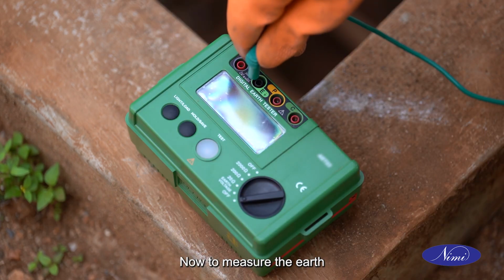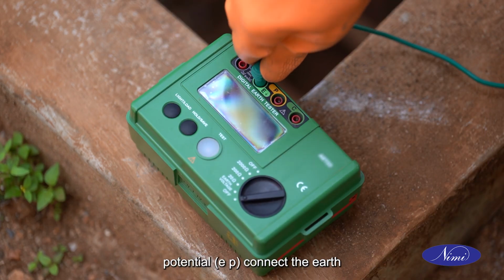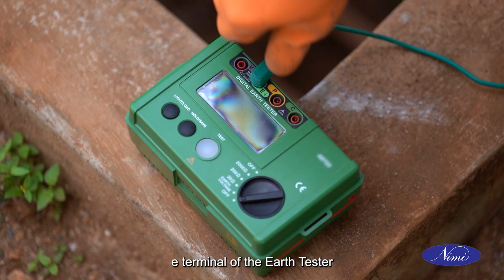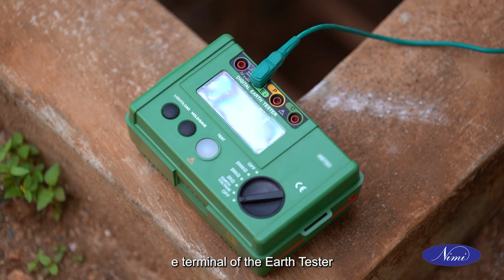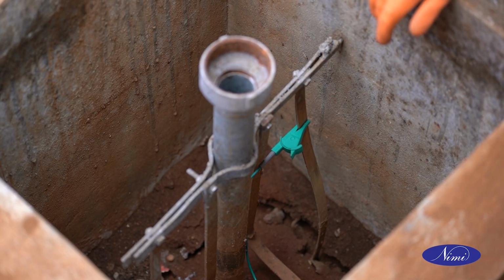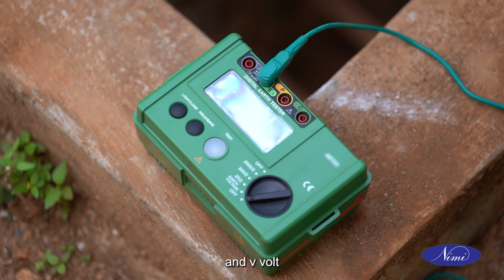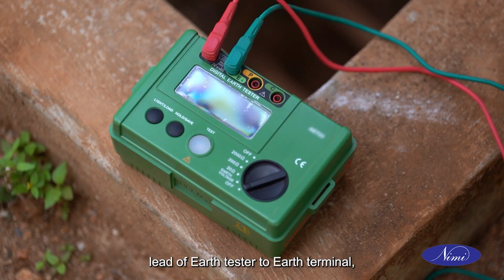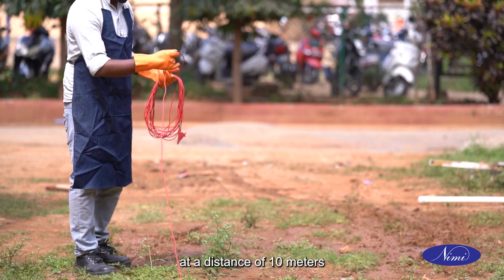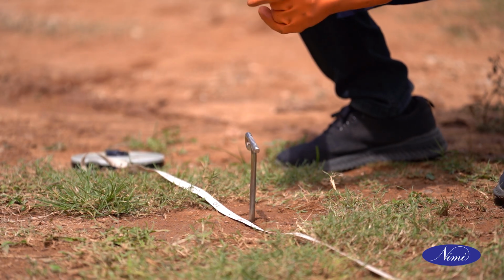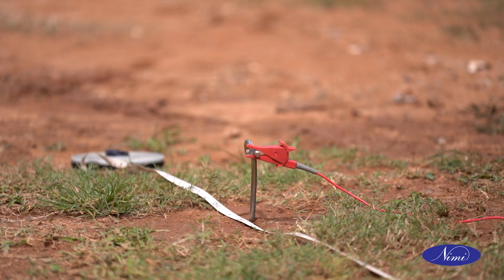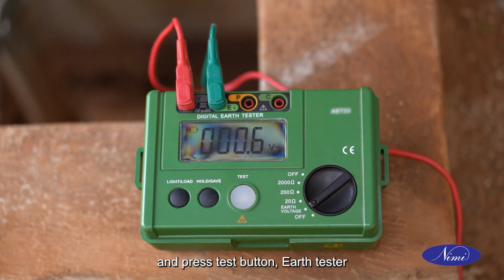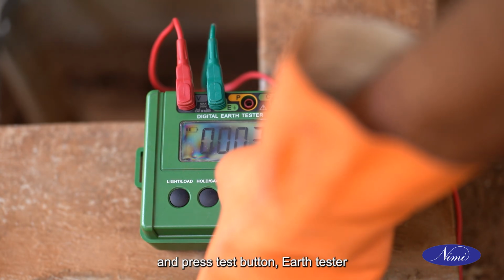Now, to measure the earth potential EP, connect the earth E terminal of the earth tester to earth wire and V volt lead of earth tester to earth terminal, which is located at a distance of 10 meters. Now change the knob position to earth voltage and press test button. Earth tester will display earth potential.